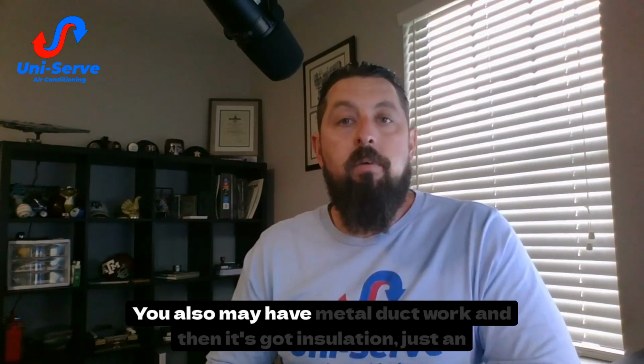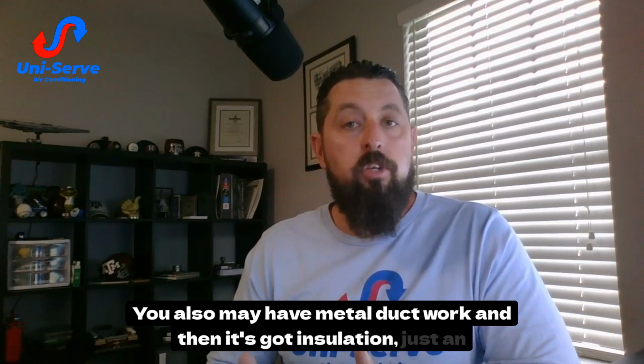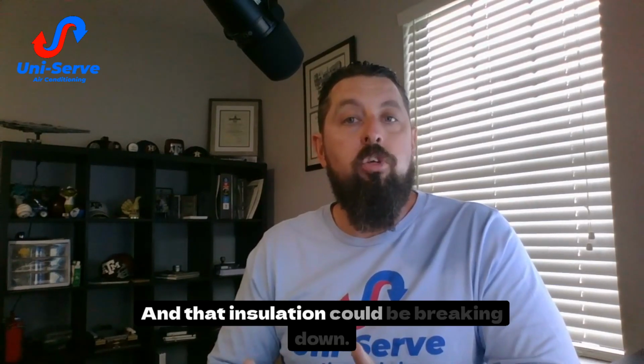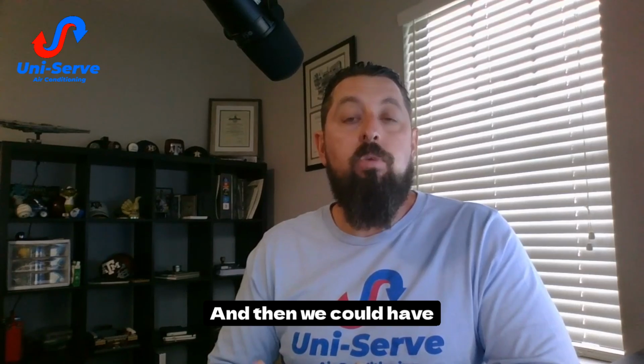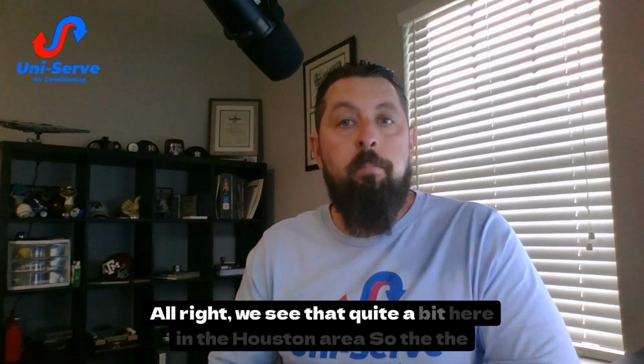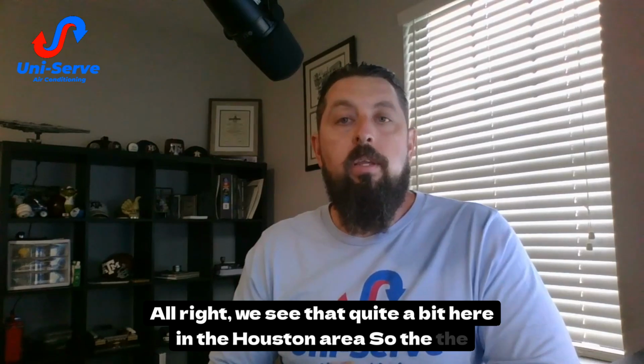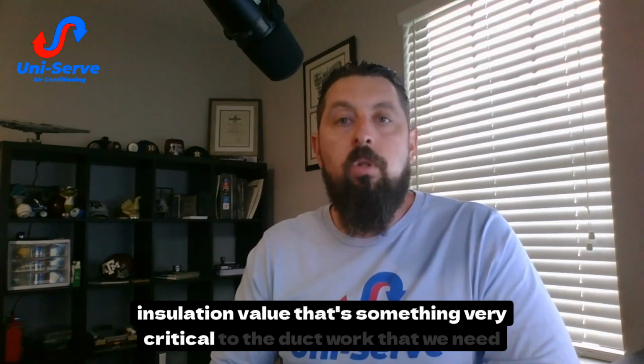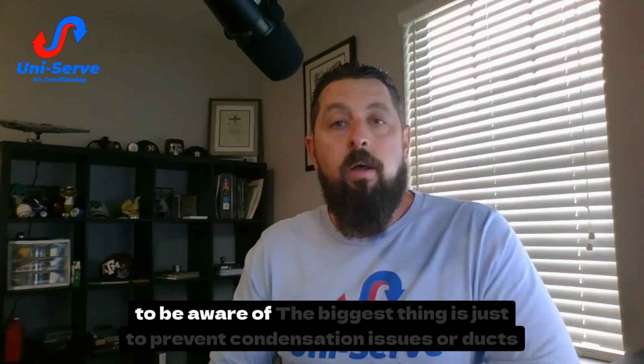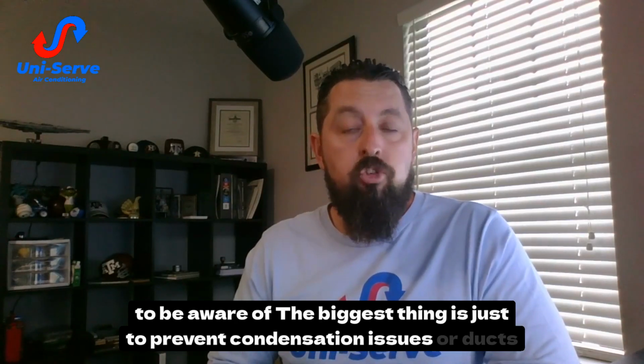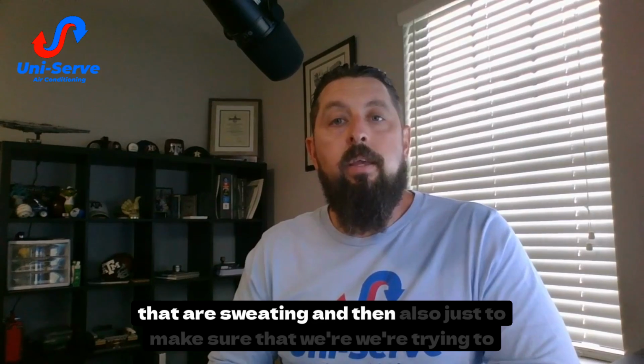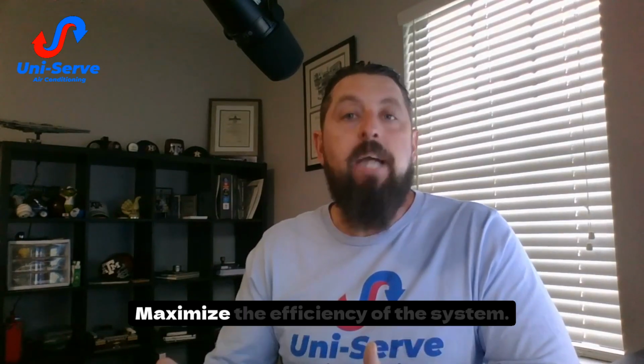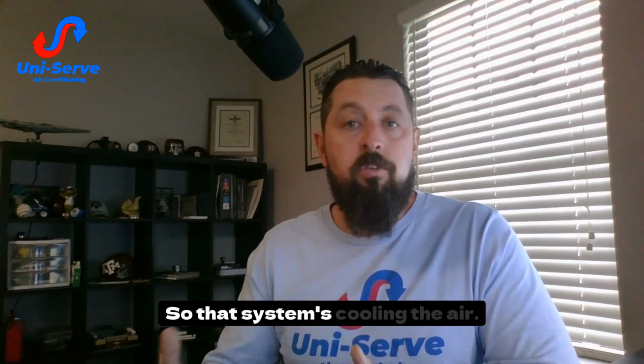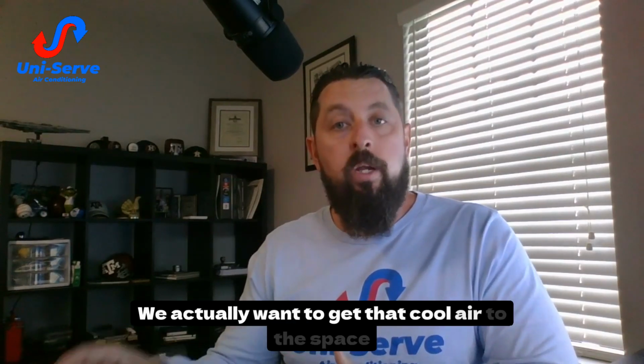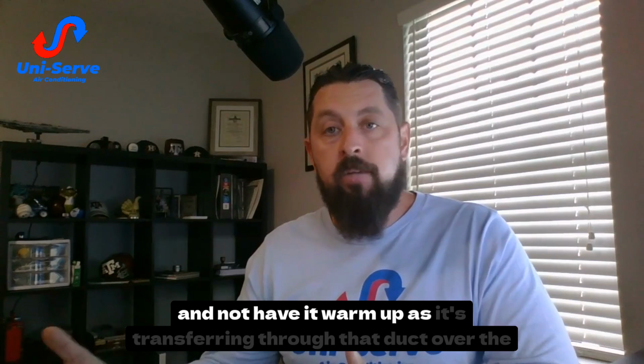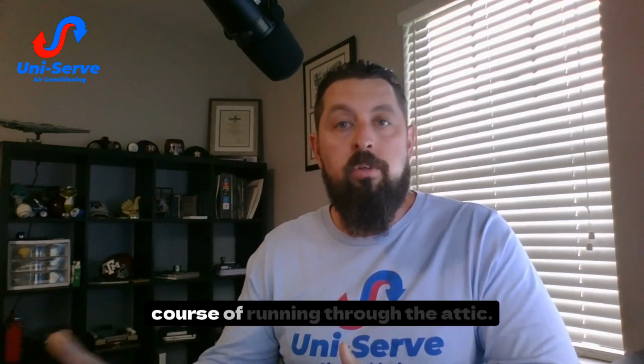You also may have metal ductwork with just an insulation wrap around it, and that insulation could be breaking down, and then we could have condensation issues. We see that quite a bit here in the Houston area. So the insulation value is something very critical to the ductwork that we need to be aware of. The biggest thing is to prevent condensation issues or ducts that are sweating, and also to make sure we're maximizing the efficiency of the system. That system's cooling the air. We actually want to get that cool air to the space and not have it warm up as it's transferring through that duct over the course of running through the attic.